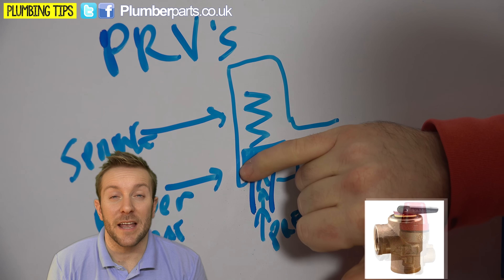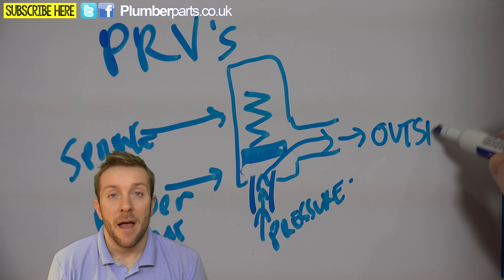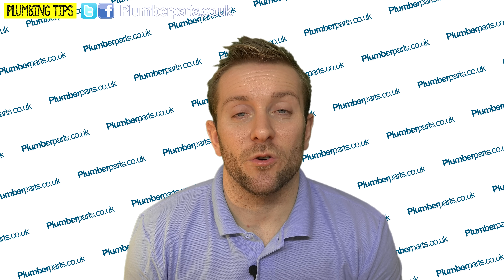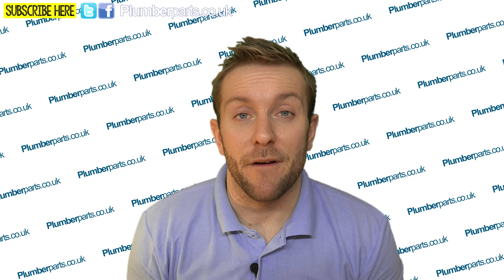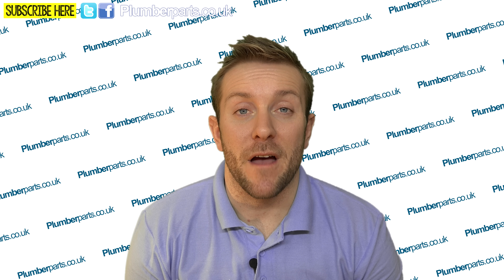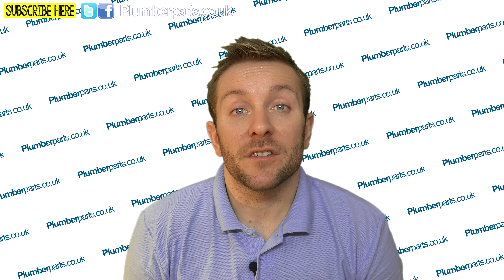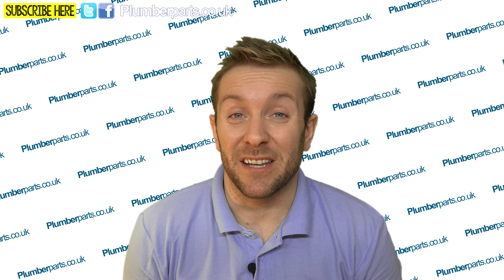Pressure relief valves are very simple — just a rubber valve with a set spring on the back. When the water gets up to a certain pressure, it pushes on that spring and dumps the water at a safe location outside. They're usually run with a little 15mm copper pipe that sticks out the back wall of the boiler, and usually the outlet is behind a hedge or somewhere you can never see them running or dripping. So if you've got a problem with the expansion vessel, the pressure will go up so much that it starts dumping out of the pressure relief valve and your pressure drop happens that way. A specific problem with the pressure relief valve is that the spring will get weaker and weaker over time — about 50% of pressure relief valves fail after about 10 years. They'll start to slowly drip outside where you're not looking. So pop outside, find that little 15mm pipe, run your finger under it and see if it's wet. If it is, you've probably got a problem with the pressure relief valve and you'll need to get a plumber out to replace it.